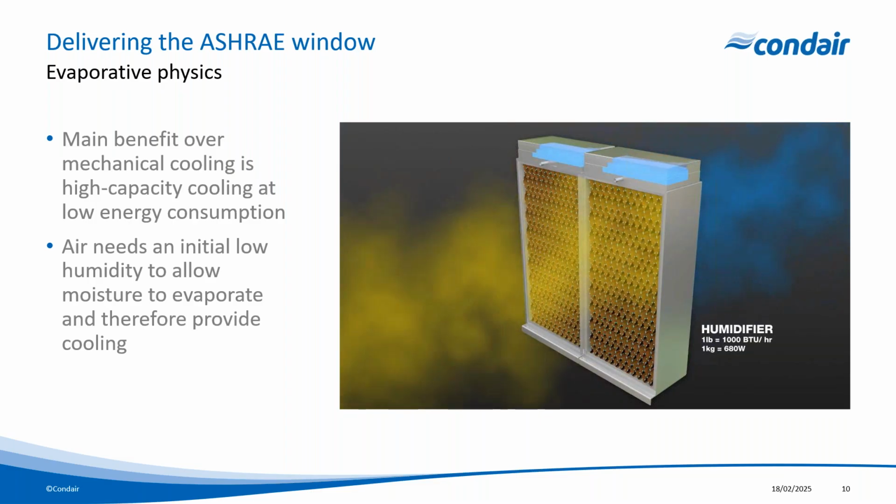So we're taking water and converting it from its liquid state to its gaseous state, and to do this requires a certain amount of energy. The energy in this case is heat energy from the airstream, which is transferred to the water, resulting in a decrease in air temperature, as well as an increase in moisture content.